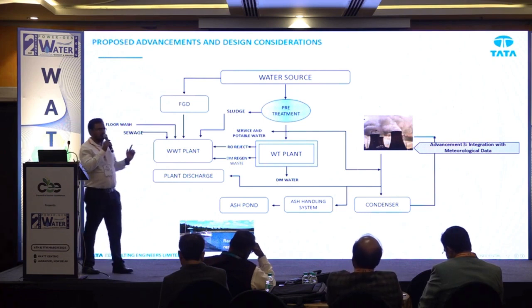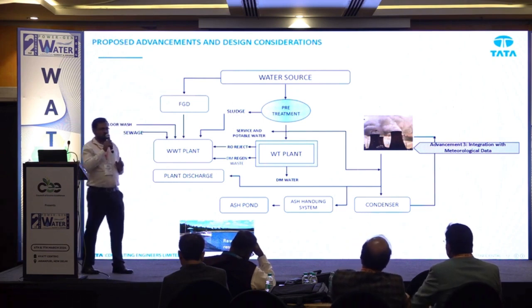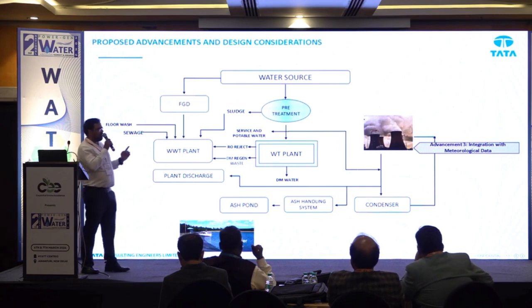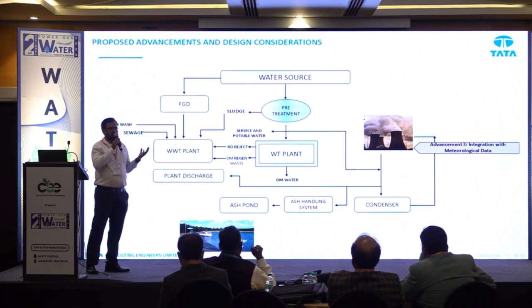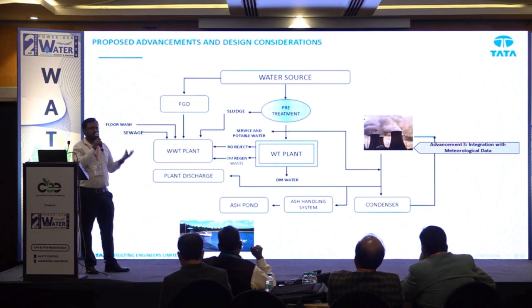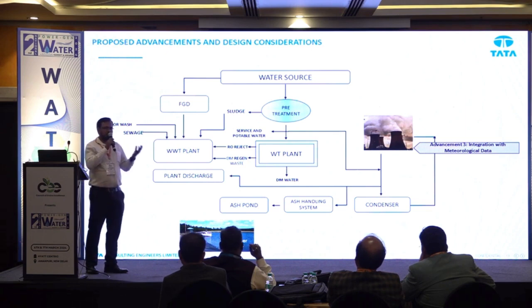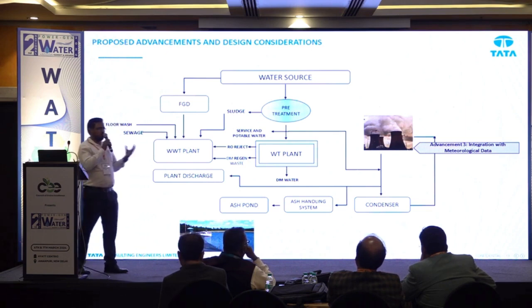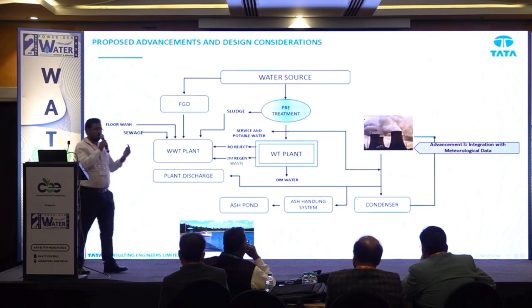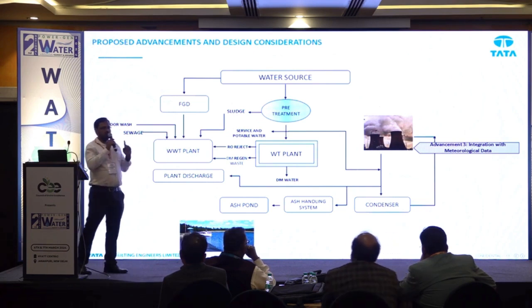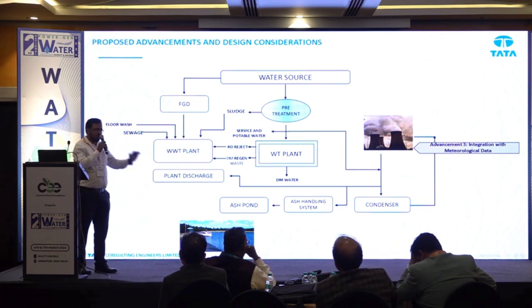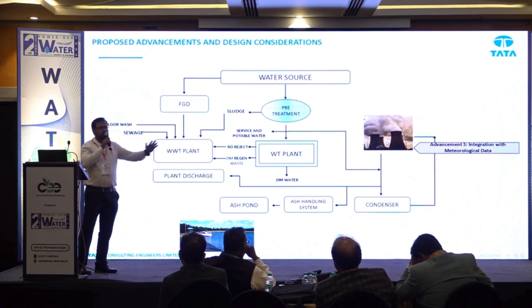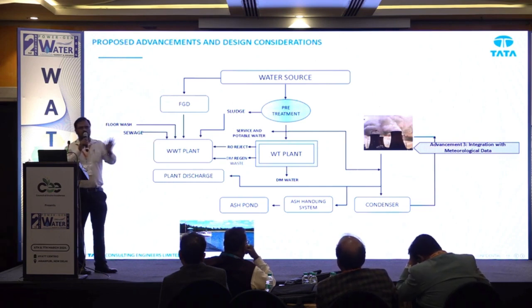VFD will operate based on input data from meteorological changes, variation in day and night, any time, and based on the input of the simulation. So with these three, we will be able to reduce the fan consumption. It will optimize the fan rotation, RPM, and based on the input, it will operate. So it will reduce the power consumption, but not only power consumption.